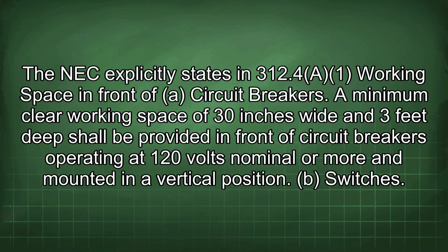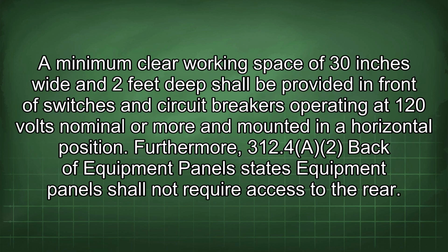For switches, a minimum clear working space of 30 inches wide and 2 feet deep shall be provided in front of switches and circuit breakers operating at 120 volts nominal or more and mounted in a horizontal position. Furthermore, 312.4(A)(2) Back of Equipment Panels states equipment panel shall not require access to the rear.